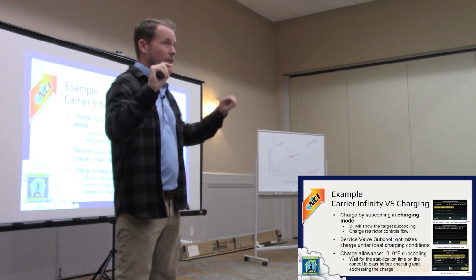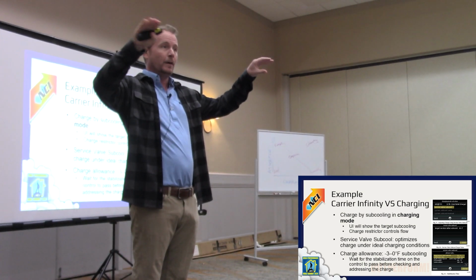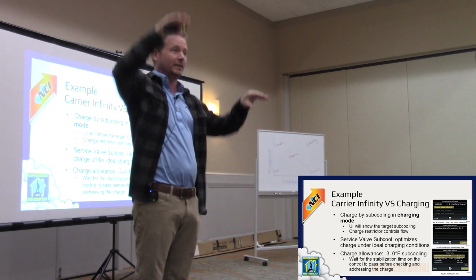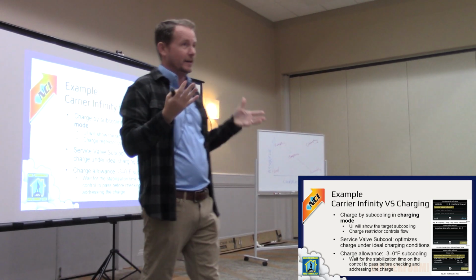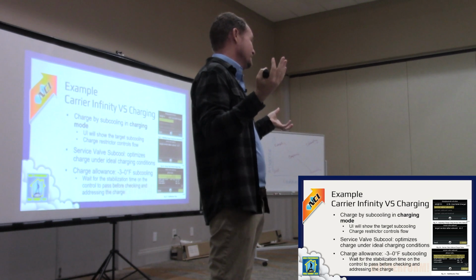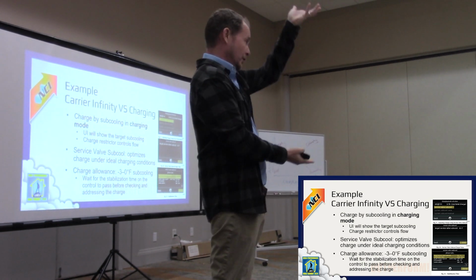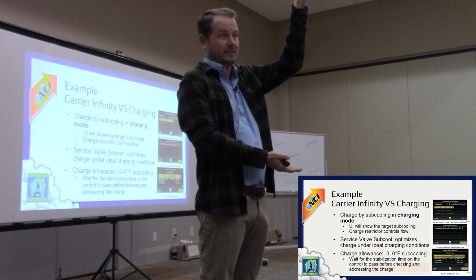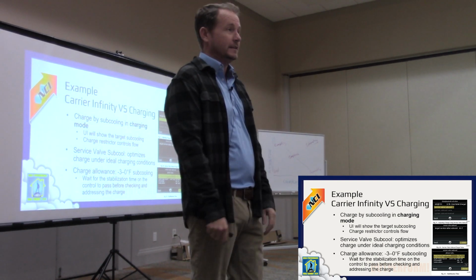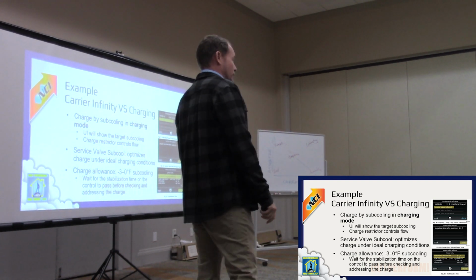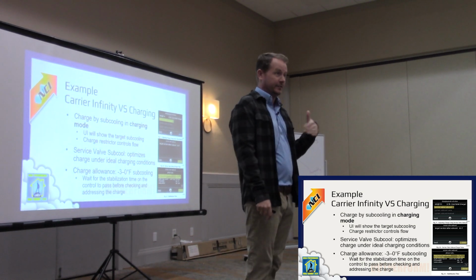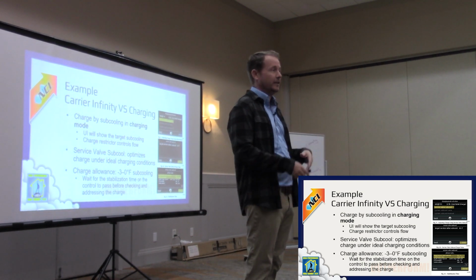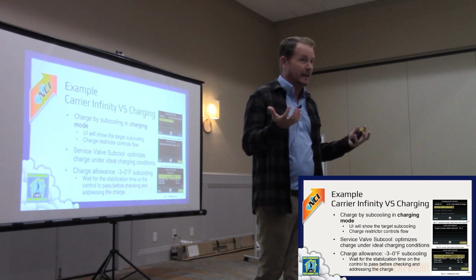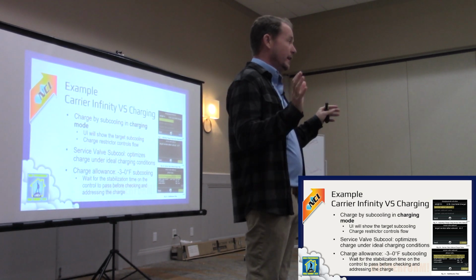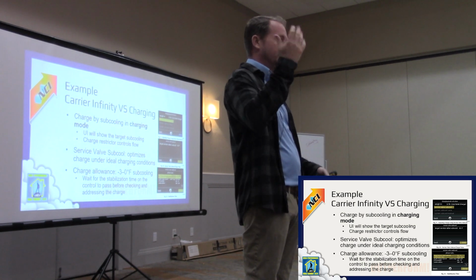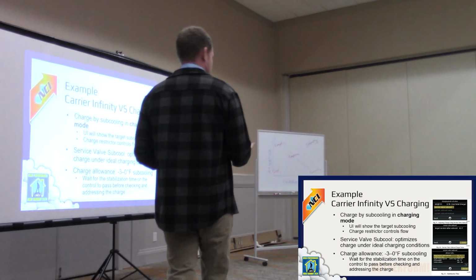It varies - it depends on whether it's a long line and they're at the same level, or whether the evaporator is above the condenser or the condenser is above the evaporator. There's crazy cool stuff you can learn, like static regain on your liquid line. In cases where your evaporator is below your condenser, you can actually downsize the liquid line in some cases significantly. So if you're working on a big apartment complex and you want to reduce the overall total system charge and reduce your copper costs, you can do that, and it's completely valid in that case. Again, we don't want more refrigerant in the system than we need - that's really no good, it causes all kinds of issues. One of the big issues with long lines is now you've got oil return issues, and now you've got more refrigerant than you potentially need.